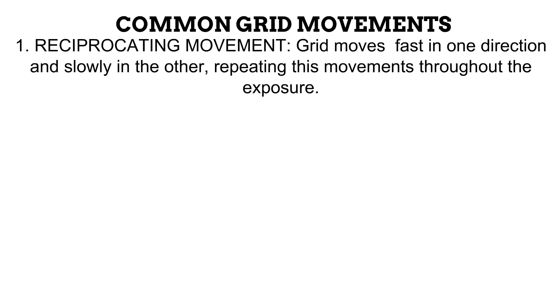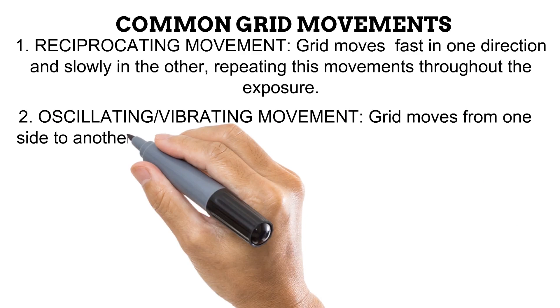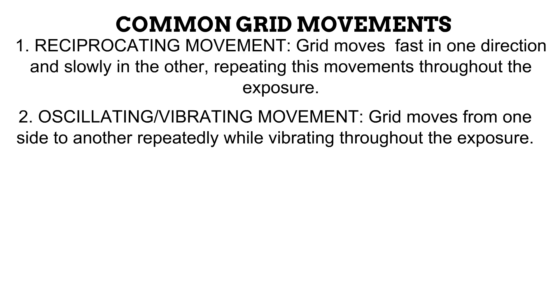Let us look at some movement types used by different Potter-Bucky diaphragms. First is the reciprocating movement, where the grid moves fast in one direction and slowly in the other, repeatedly throughout the exposure. Second is the oscillating or vibrating movement, where the grid moves to and fro repeatedly while vibrating. This vibration helps to solve a problem that occurs in the reciprocating movement known as the stroboscopic effect — when a moving grid appears stationary and still produces grid lines. Vibration helps to avoid this.